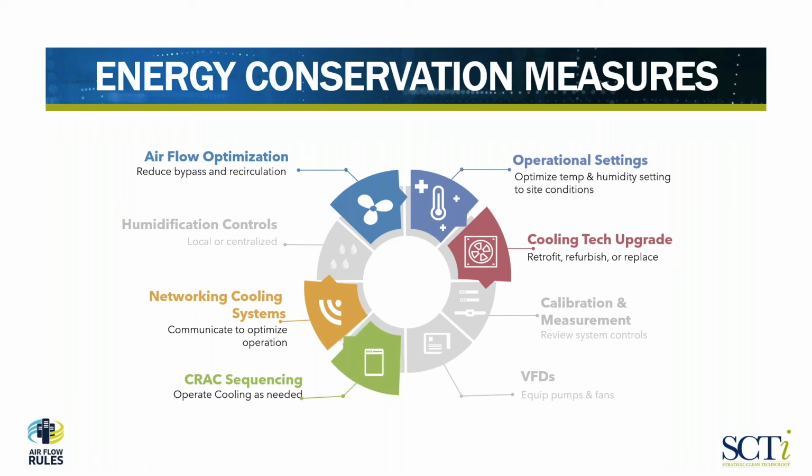And then we look at operational settings. So what's the temperature, what's the humidity set points that you have on your CRAC units? How much can we push those up? Because the higher we can push those from a temperature point of view, the more efficient your cooling unit is going to run, and equally so, the less energy it's going to consume.